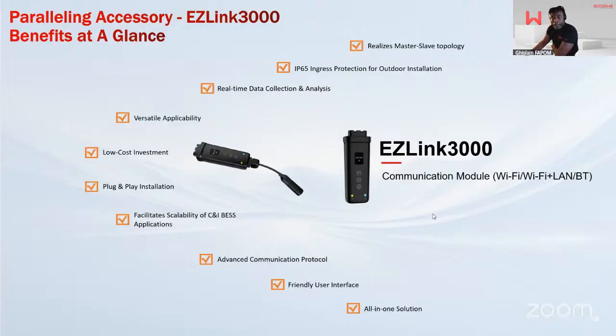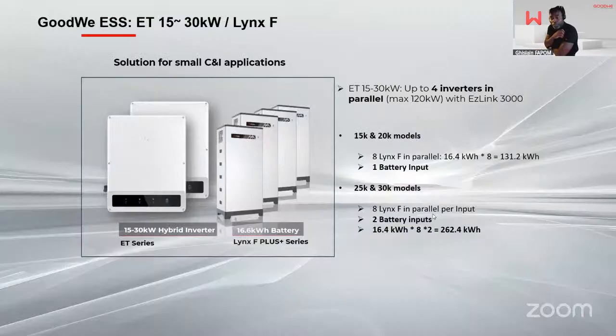And with the EZLink 3000, we'll be able, for example, to use the smaller platform ET 15 to 30 kilowatt and the Lynx F series. There are actually 3 types of Lynx F: Lynx F, Lynx F Plus, and Lynx F G2. We all put them under the Lynx F umbrella. On the smaller platform, 15 to 30 has 2 subsets. There's a subset of 15 and 20 kilowatt inverters that only have 1 battery input.